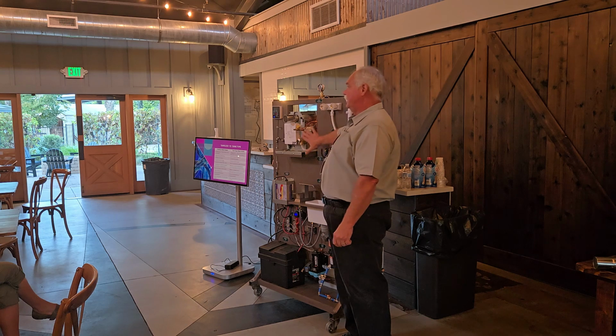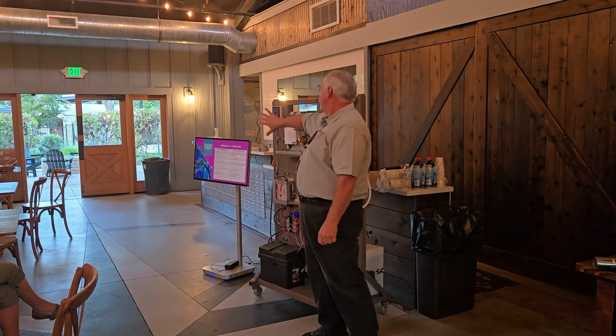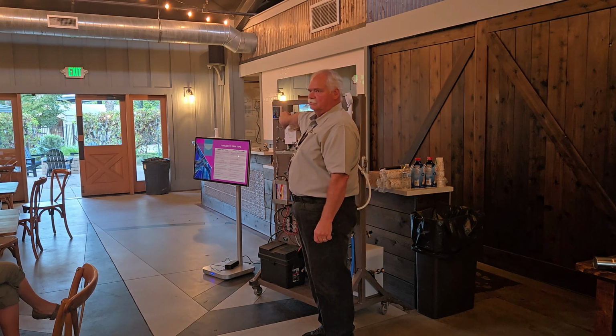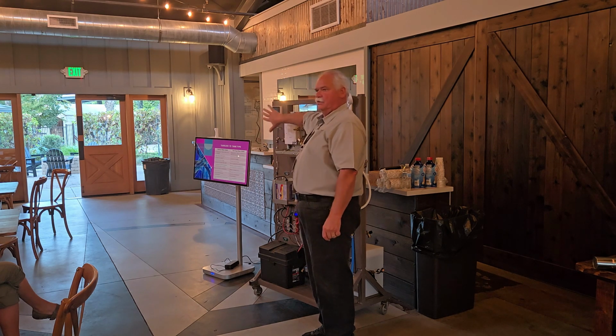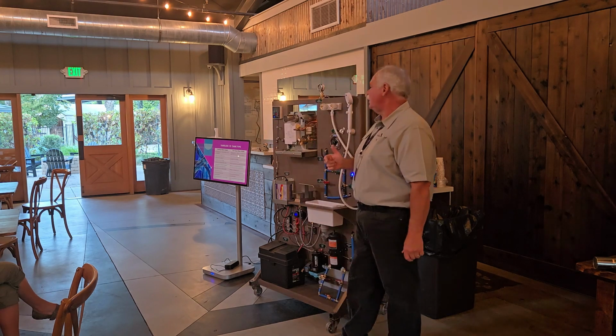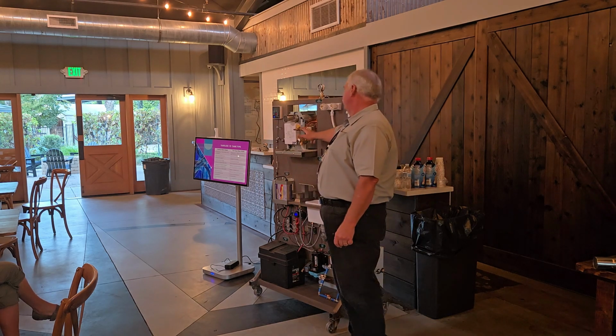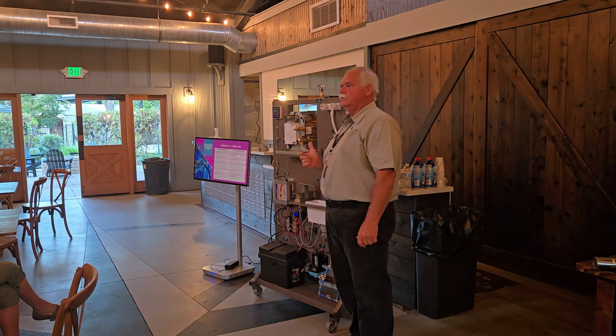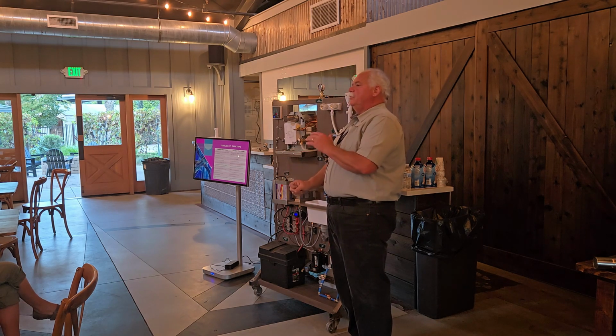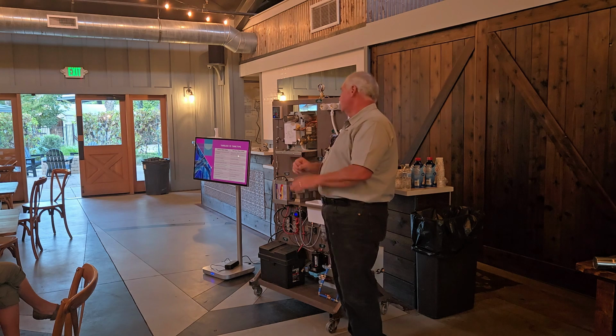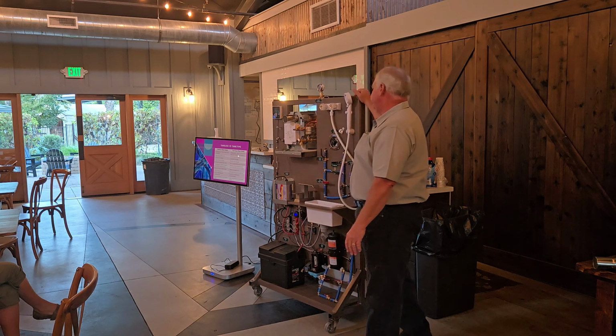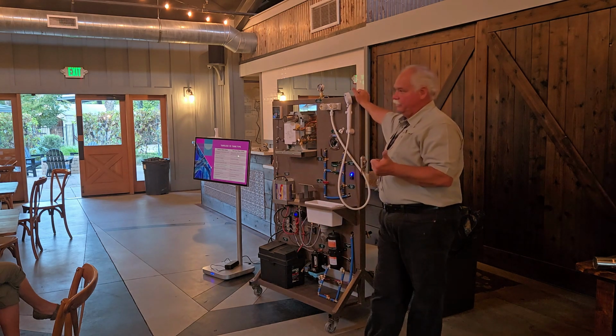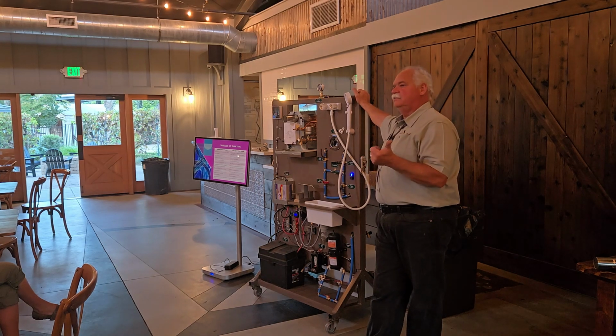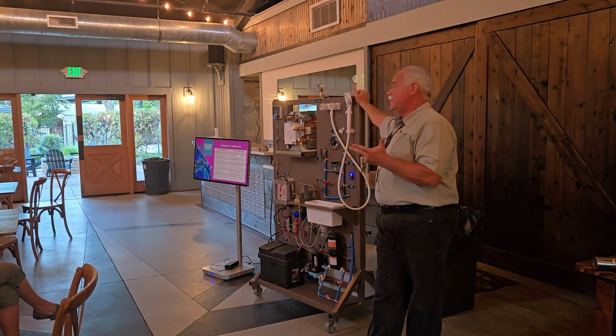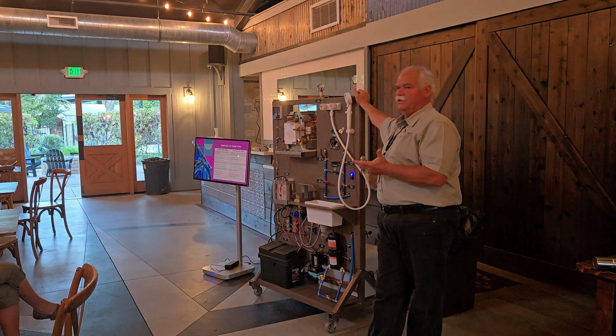So maintenance is critical on these. You want to make sure that you're getting air through the system. When this is running, I can put my hand over this, if I had a glove on, because it's going to be really hot air, and I can get this water heater shut down just by changing the airflow. So again, water flow, airflow, they're critical. So let's talk a little bit about some of the conditions that are going to cause inconsistent heat. Water flow. So we already talked about that regulator valve, that filter, maybe the size or length of the hose that you have it connected to.